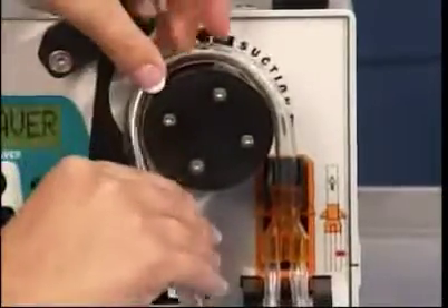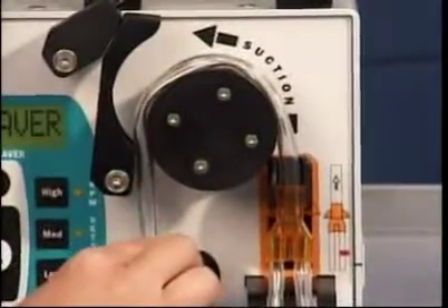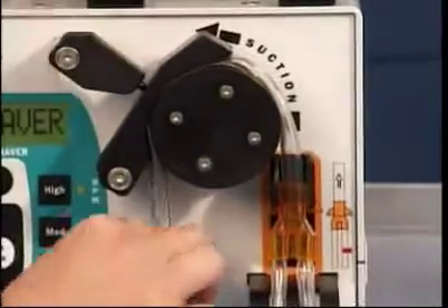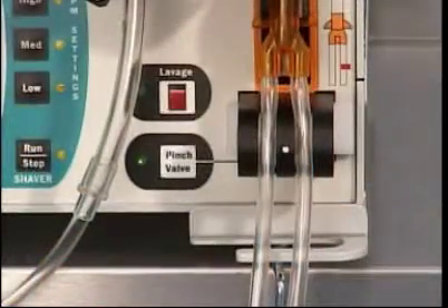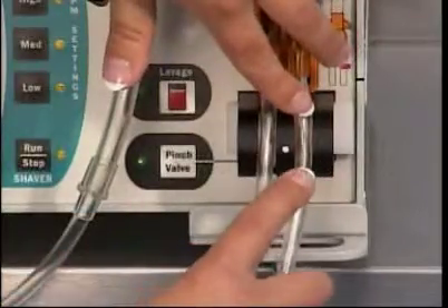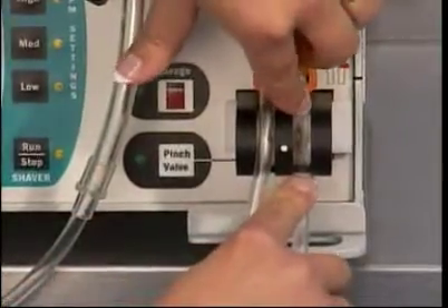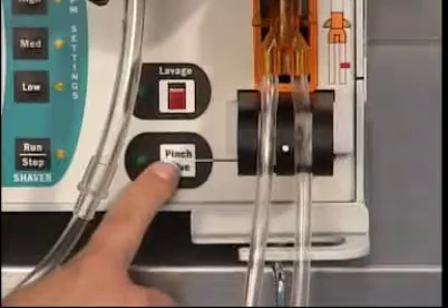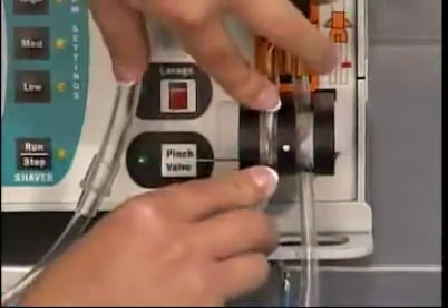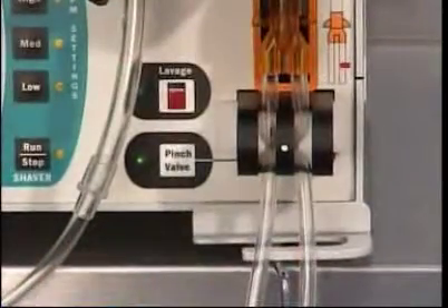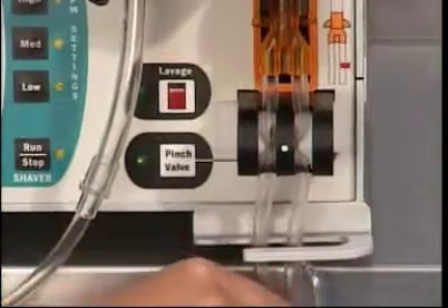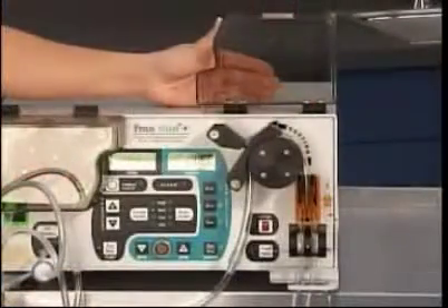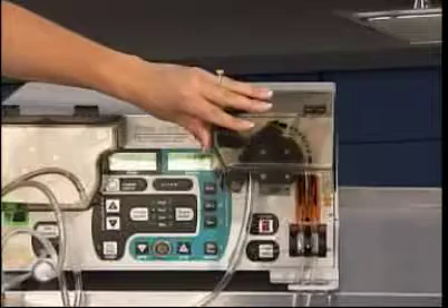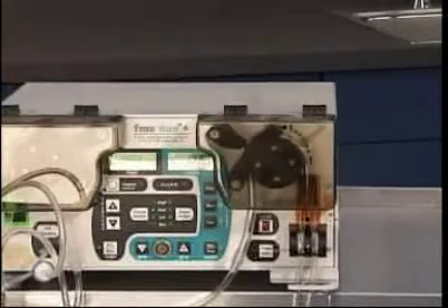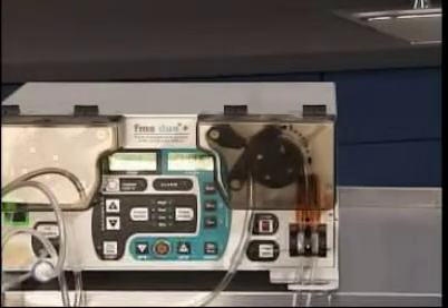Place and center tubing around the roller pump, pulling on tubing slightly, and close tension rocker and locking arm. Starting with the outflow tube, the tube closest to the outside of the pump, slide it snugly into the pinch valve slot. Press the pinch valve button and slide the other tube into this slot. Make sure both tubes are placed behind the holder under the pinch valve. Close the cover and make sure it's flush against the pump. It is important to ensure the cover is touching the pump at all times. The pump will temporarily stop working if it isn't flush.